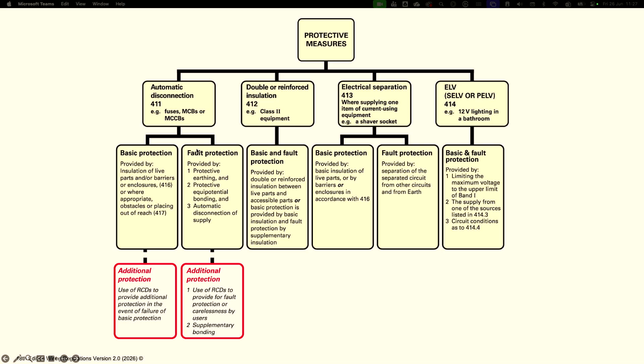As I mentioned in part one, sometimes you need basic protection and fault protection on their own. So you can't just have insulation - you need insulation and barriers and enclosures, and you also need fault protection, so fuses, circuit breakers, RCDs or something like that. You put the two together, and then you get the protective measure. So be familiar with that one.